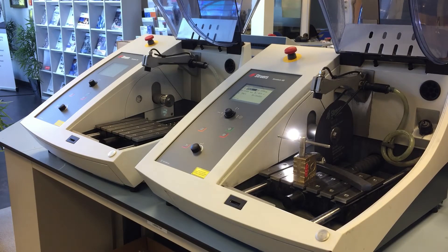Today we're going to show you our Secotom-60 Bench Top Precision Cutting Machine. The 60 is the top of the range machine which allows you to use automatic accessories like the X-Table. It comes with a laser to allow you to accurately line up cuts, and it will take our full range of cutting wheels up to 200mm in diameter.